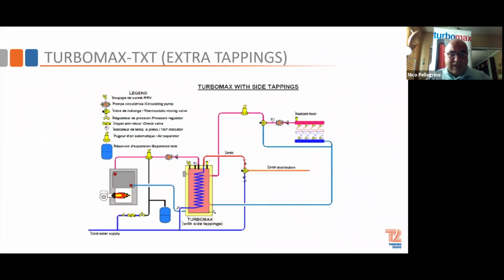So the Turbomax also has an option of TXT, which is extra tappings on the side of the tank. So now it becomes a true buffer and domestic production all in one tank. Now it's an option, and they're the same size as the boiler tappings. So if they're 1.5 inches, these will be 1.5 inches. So basically, again, it's a built-in buffer for your boiler. You have little micro loads or mini loads, which can happen a lot in residential. This is ideal, and if space is a problem, this will solve that problem for you.